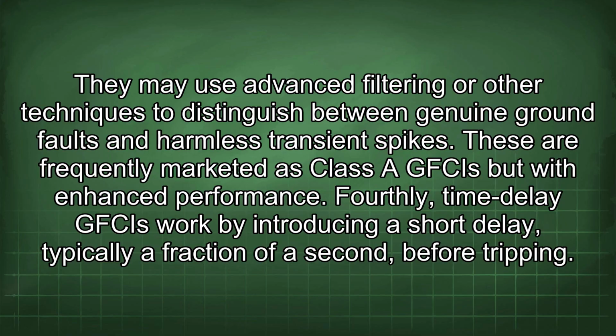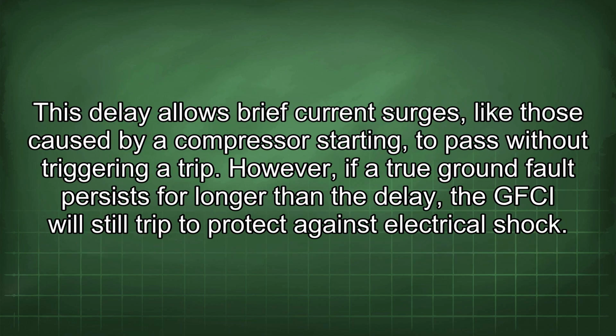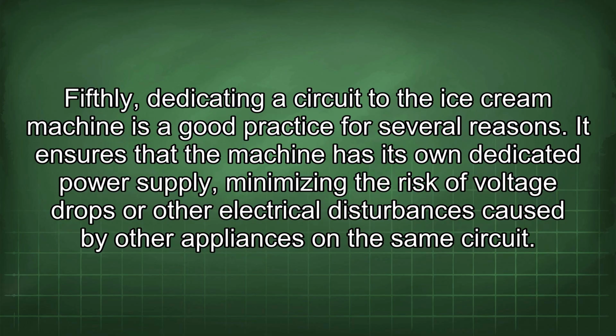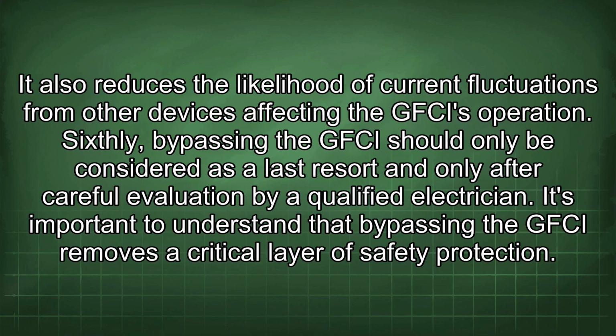Fourthly, time delay GFCIs work by introducing a short delay, typically a fraction of a second, before tripping. This delay allows brief current surges, like those caused by a compressor starting, to pass without triggering a trip. However, if a true ground fault persists for longer than the delay, the GFCI will still trip to protect against electrical shock. Fifthly, dedicating a circuit to the ice cream machine is a good practice for several reasons. It ensures that the machine has its own dedicated power supply, minimizing the risk of voltage drops or other electrical disturbances caused by other appliances on the same circuit. It also reduces the likelihood of current fluctuations from other devices affecting the GFCI's operation.